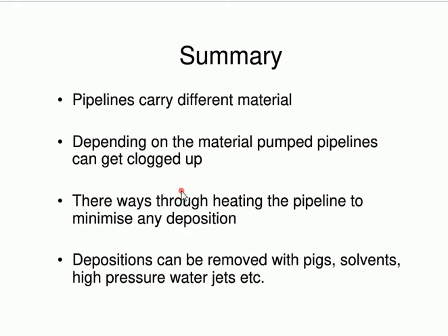But when I was talking to the veterans of sewage work, and I was asking them what was happening in winter time, whether it would ever freeze up and then the whole system wouldn't work, they said no, because most of the water is warm anyway. It comes from a domestic environment and gets heated up with the temperatures in the house, and in wintertime, even when it's really, really cold and you've got minus degrees, it always seems to be about 4, 5, 6, 7 centigrade, even in the worst of winters. So the temperature never goes really cold to the point that it freezes up.